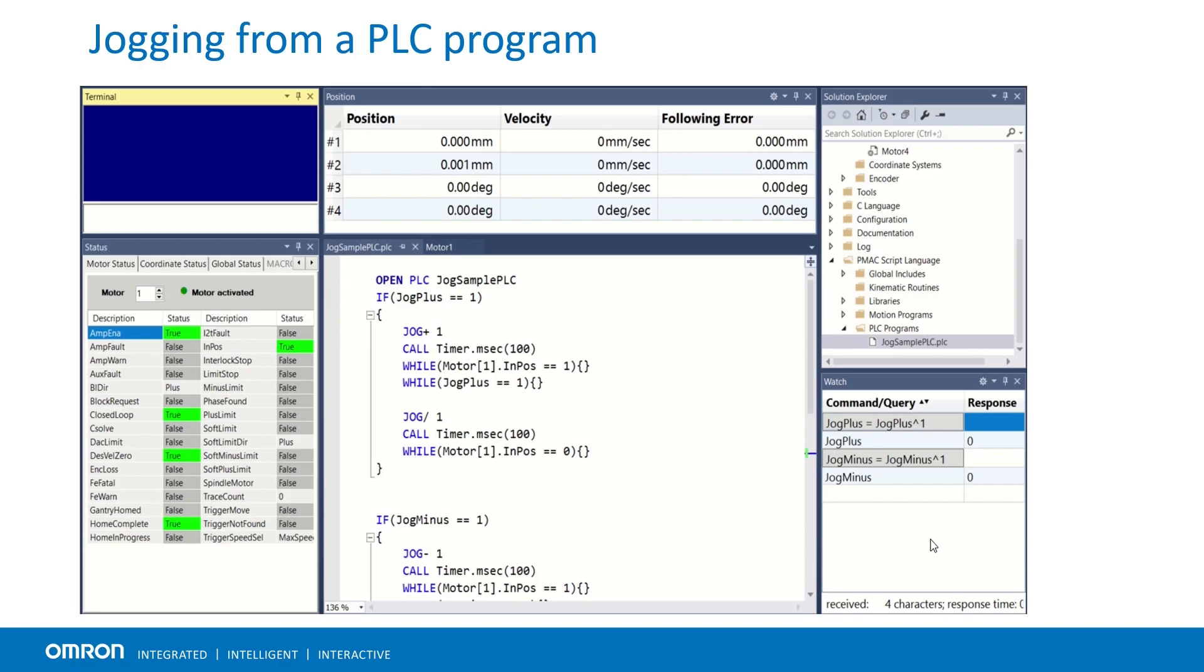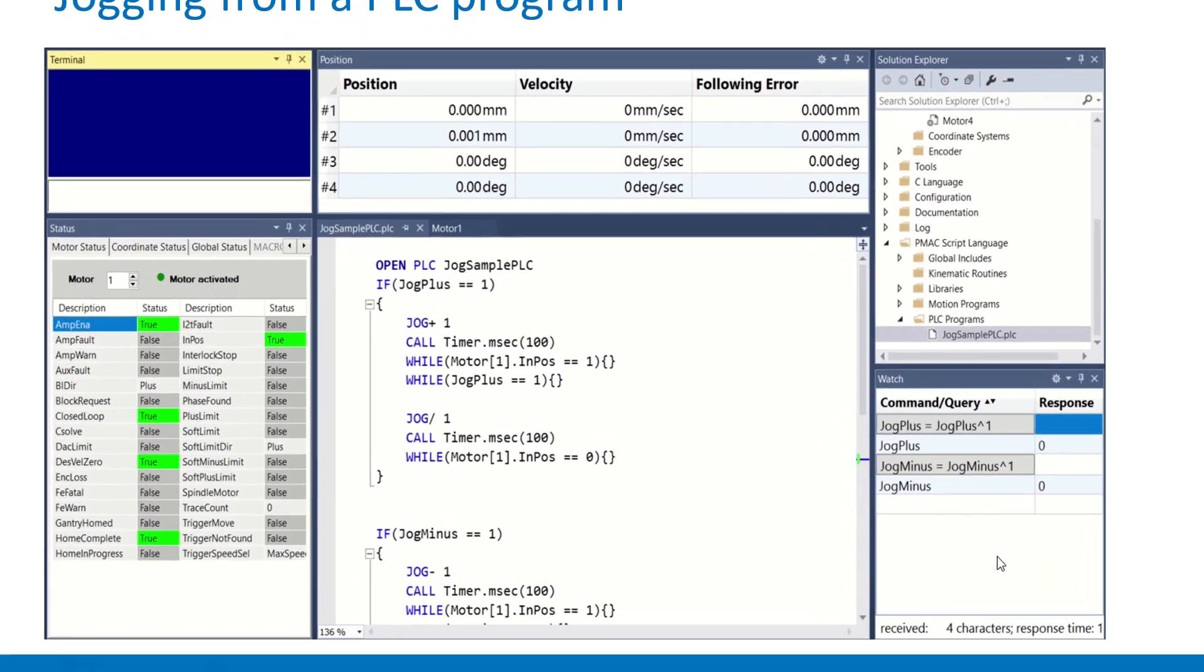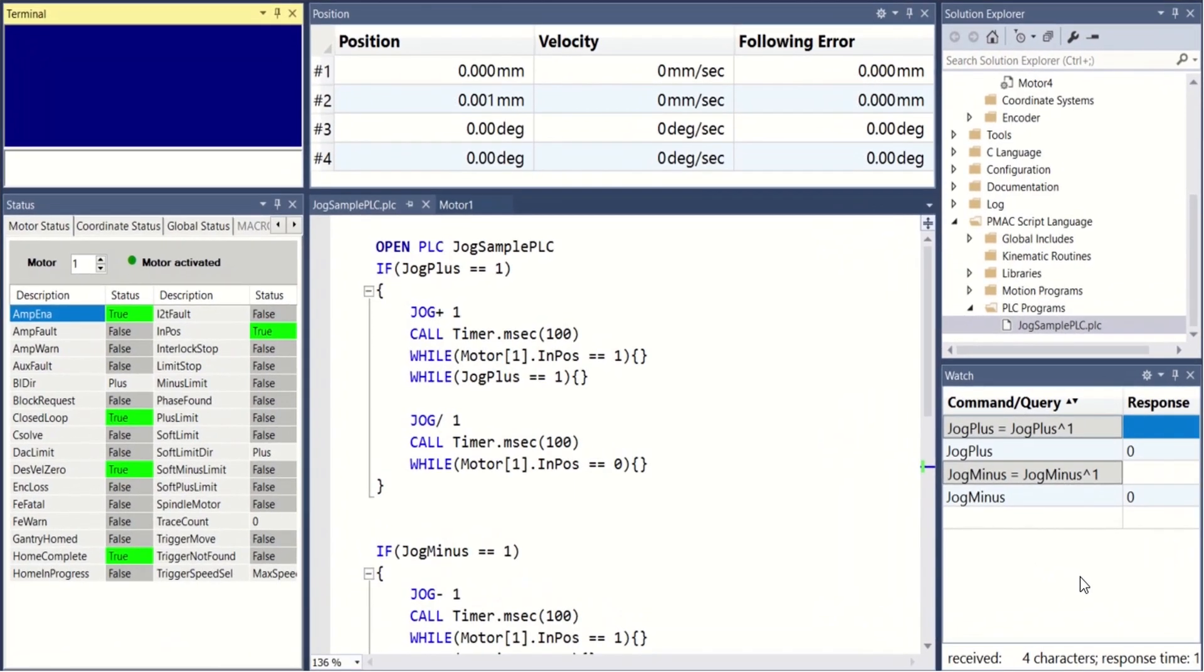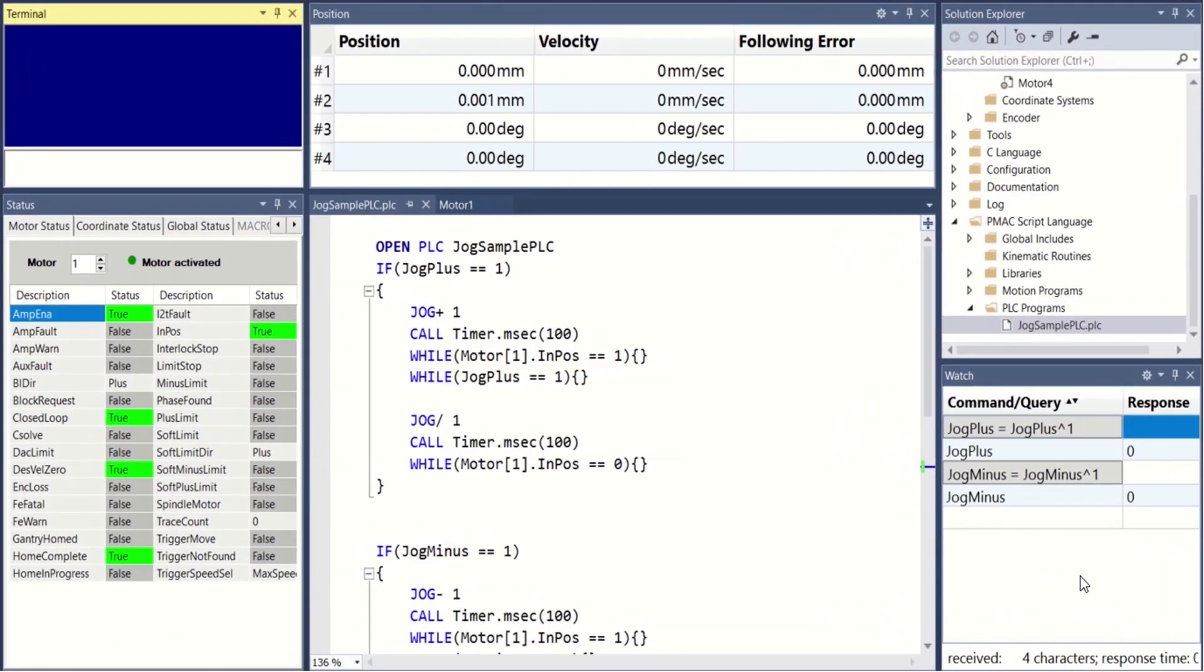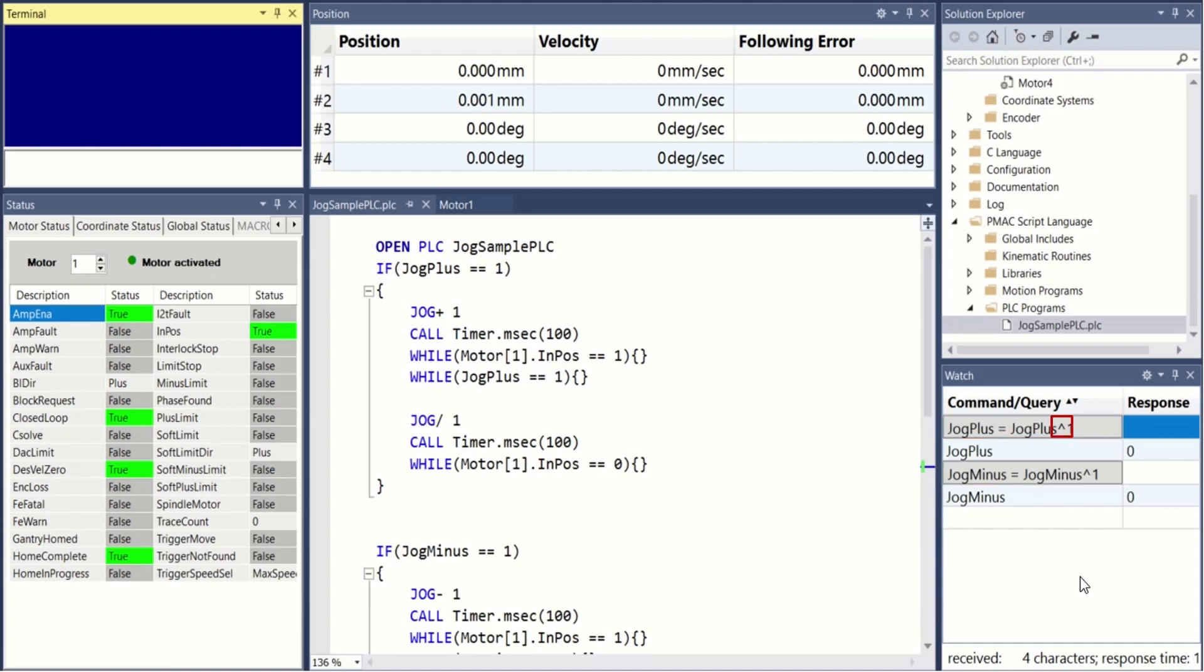Jogging a motor properly from a PLC requires a few simple but important considerations, such as checking status bits and using time delays. In order to demonstrate this, user variables jog plus and jog minus are inserted in the watch window with an exclusive or operator, creating two software toggle switches that change state every time they are pressed.